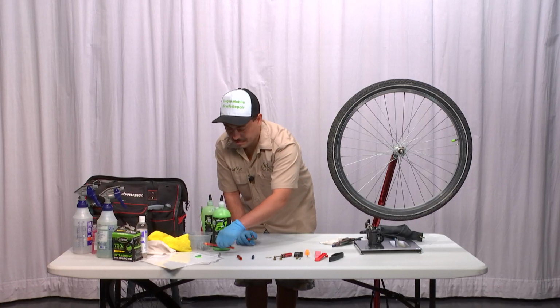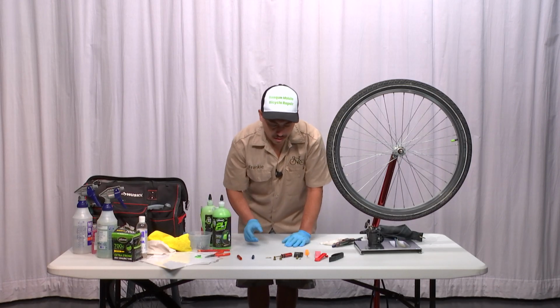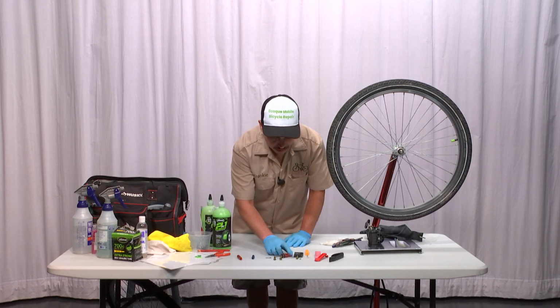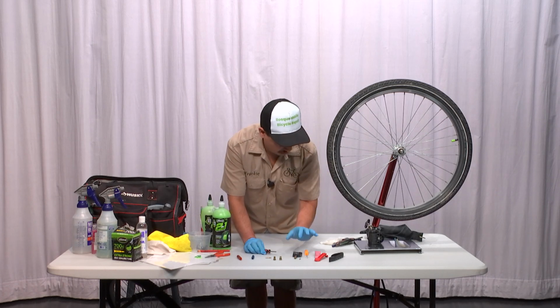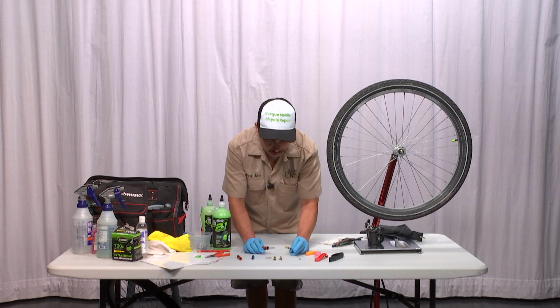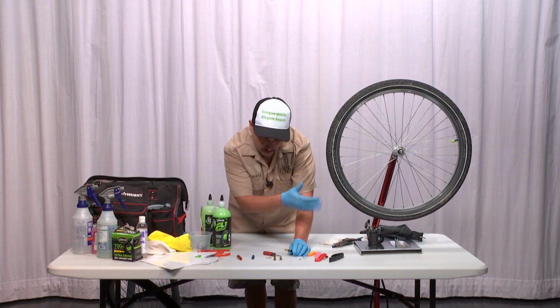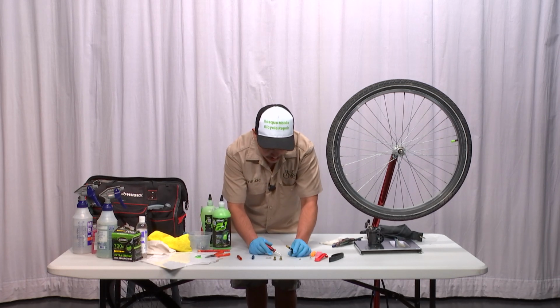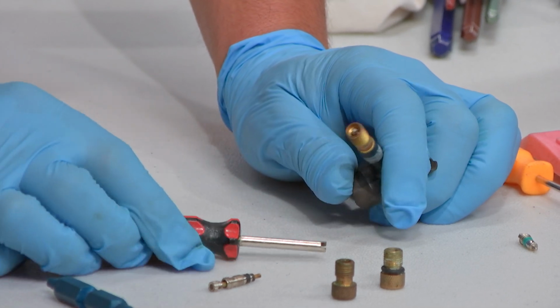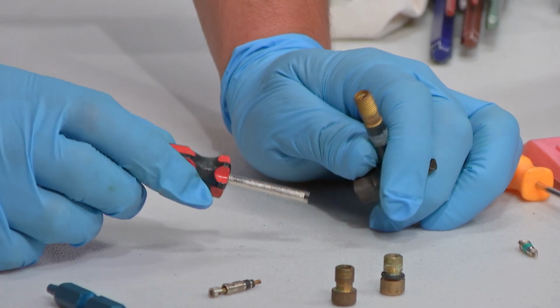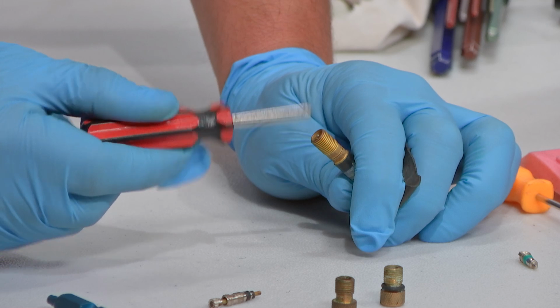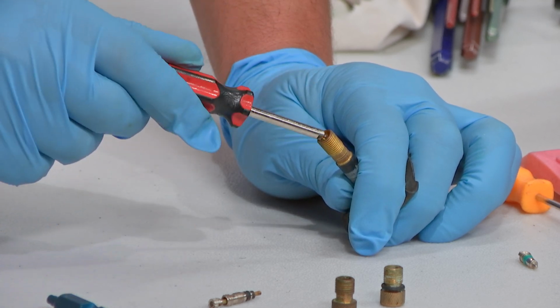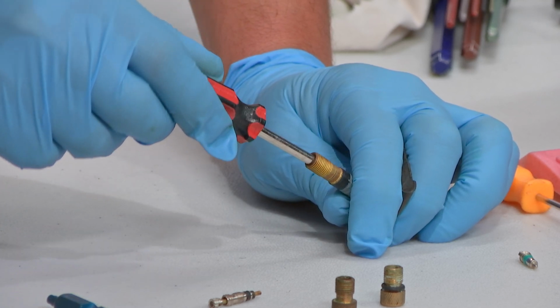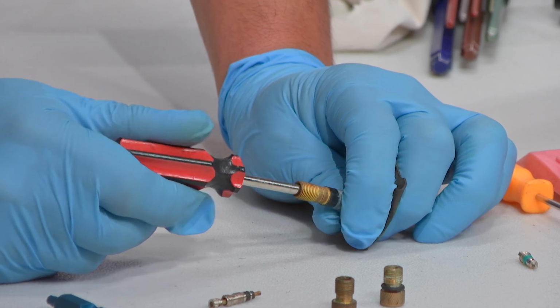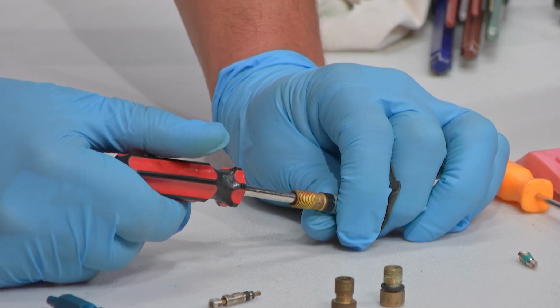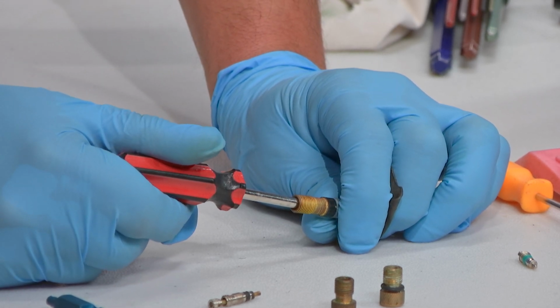Okay, so I'm going to show you—this is the valve core. We're going to do a close-up shot, then I'll do the whole procedure. This is the Schrader valve, and I'm going to remove it with the valve core removal tool. It's notched, so you just turn it until it's placed over the valve core.